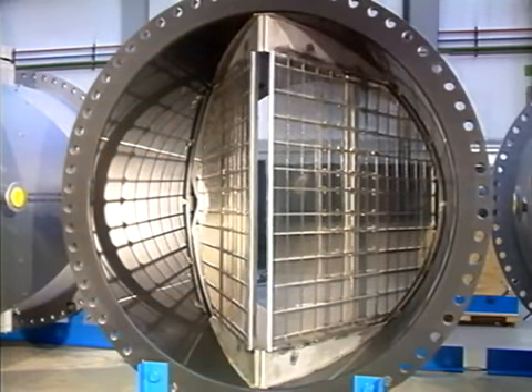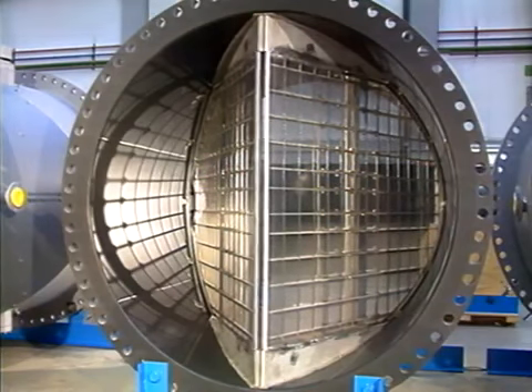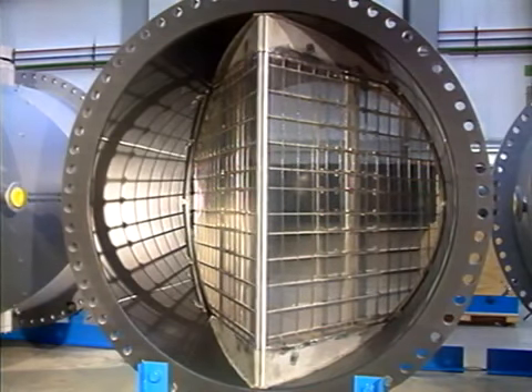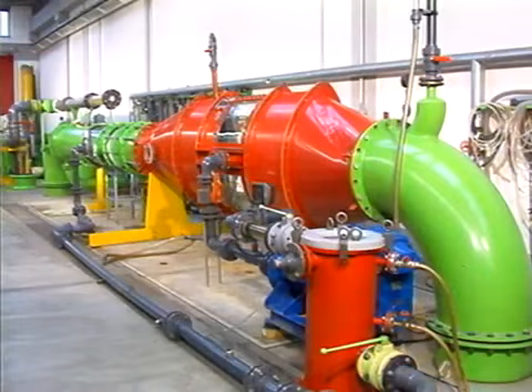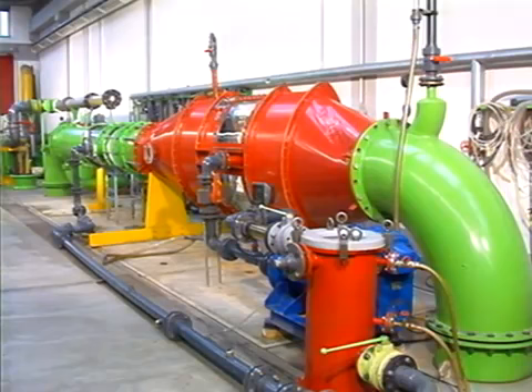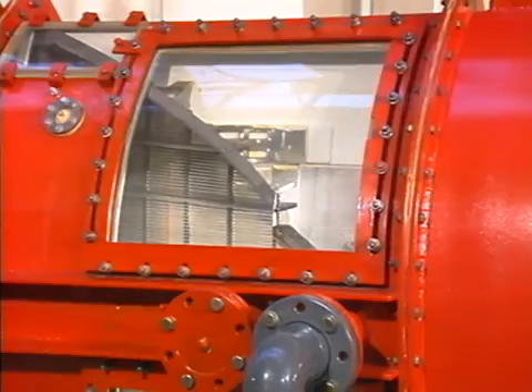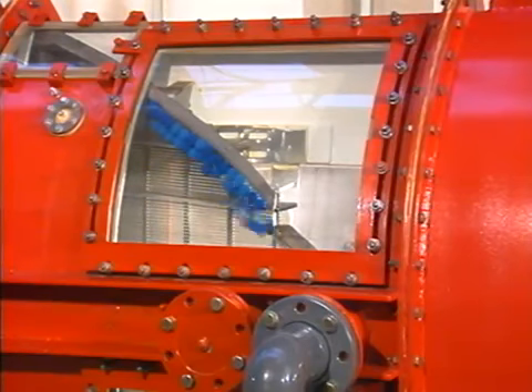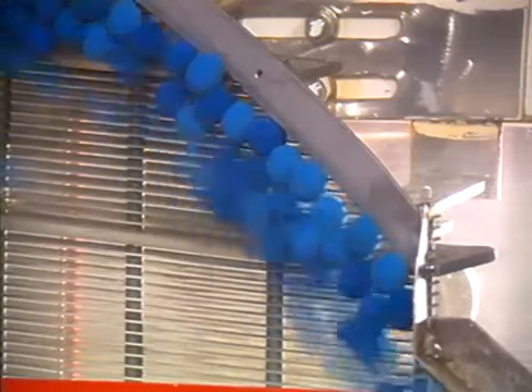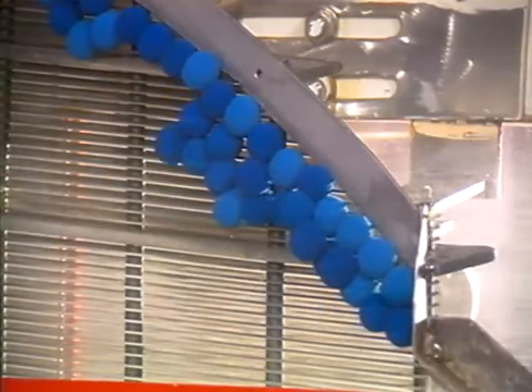Here, strainer type D2 with 2 screens inclined like a roof. The apex of the screens points into the cooling water flow. Extensive tests were conducted at TAPROGGE to optimize the transport of the balls off the screen surface. It was found, for example, that the balls tended to run along the straight bars of the screens and then stick at the bar ends between the screen and the tube wall.